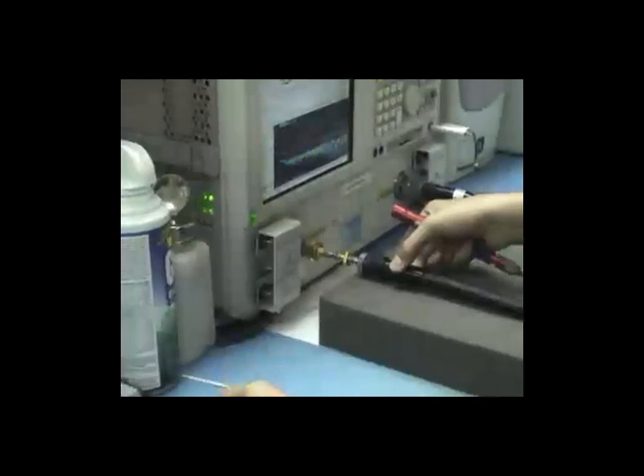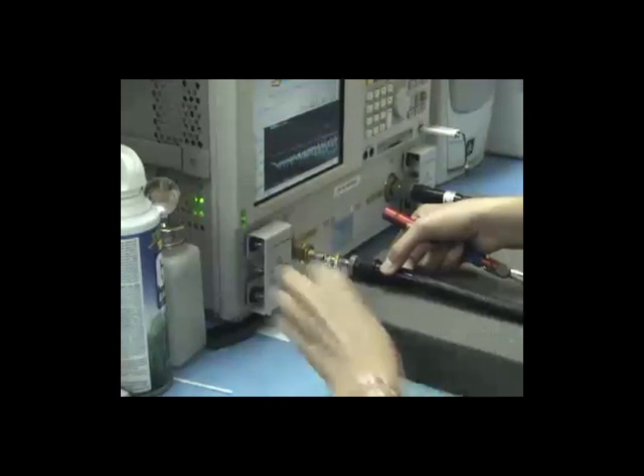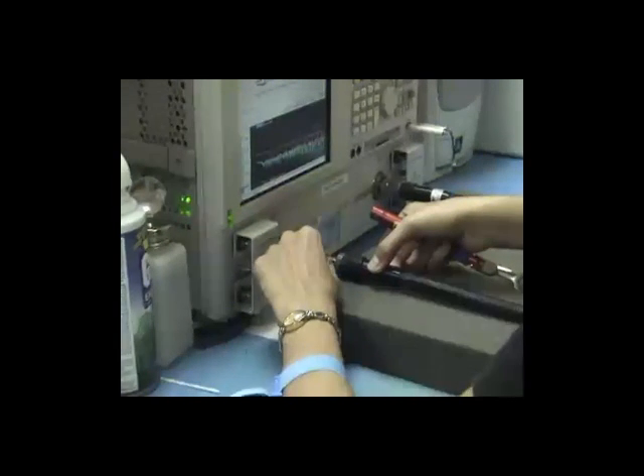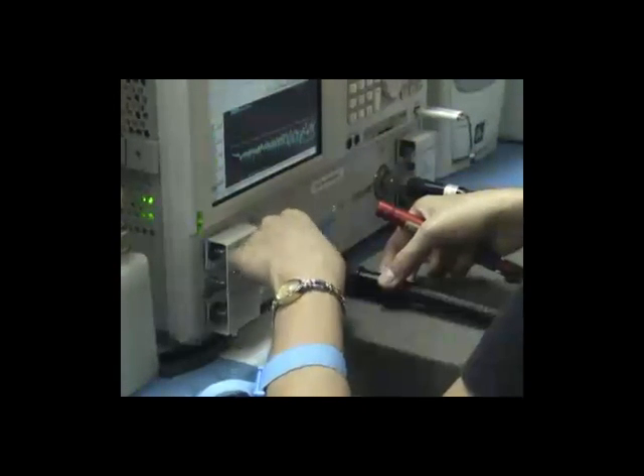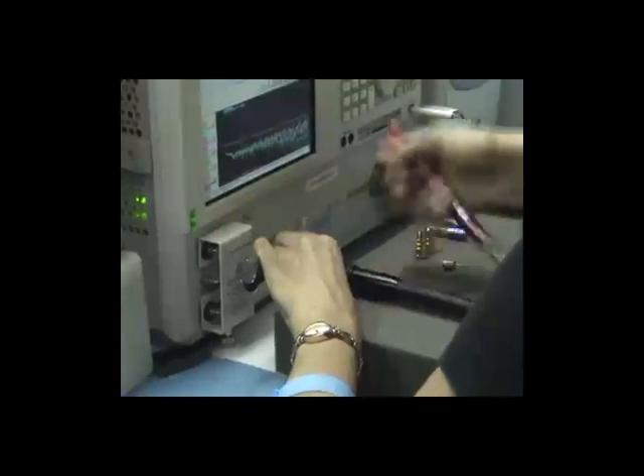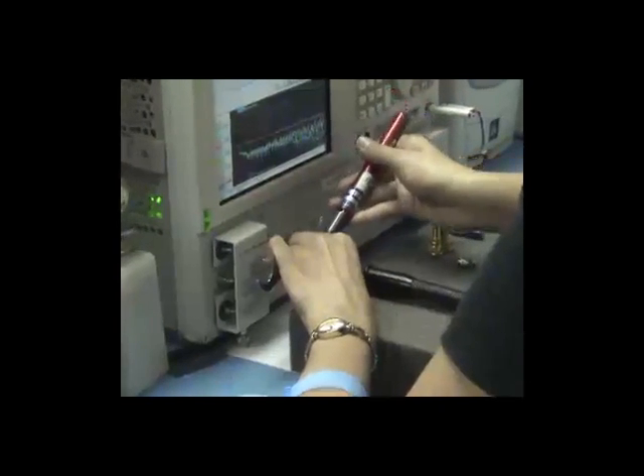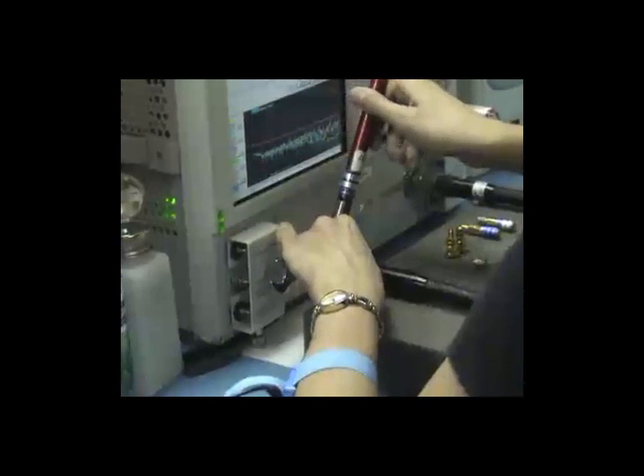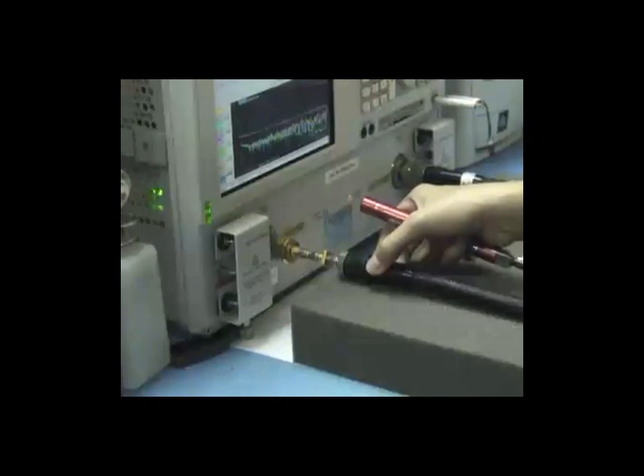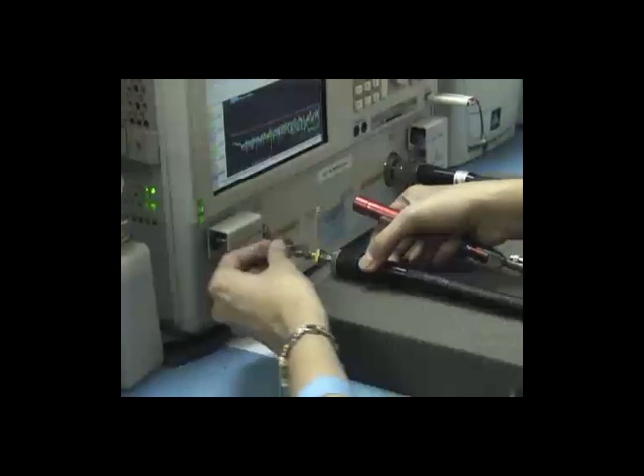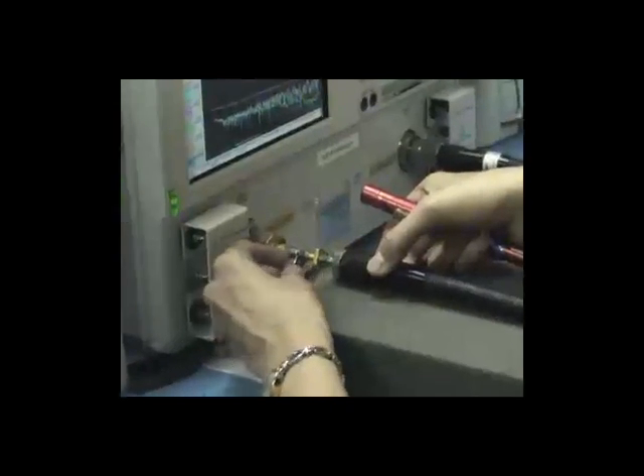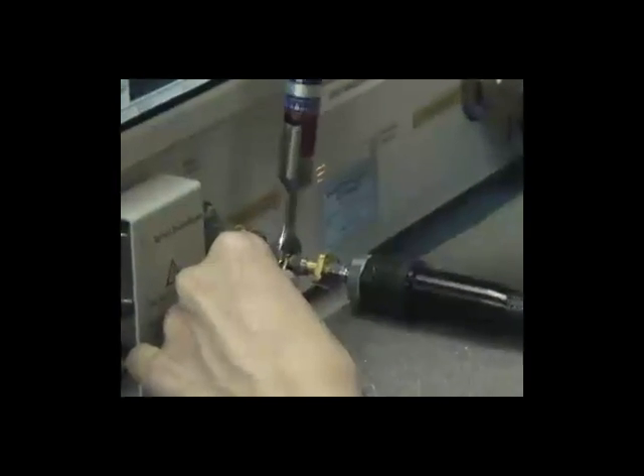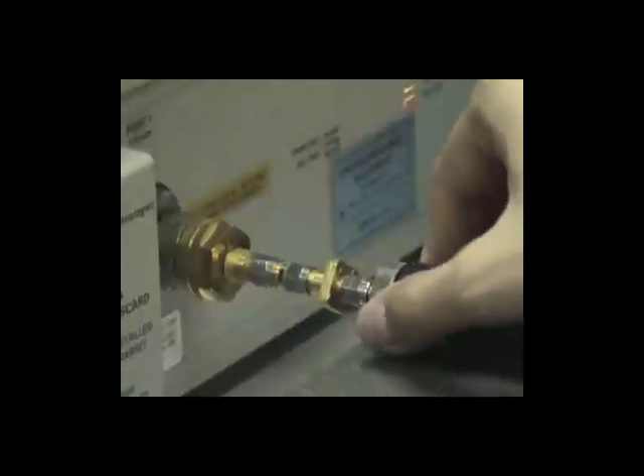Make sure you're always supporting it until you have torqued both sides, because if you haven't torqued and you let go one side, the weight of it is going to pull it. The reason why I generally go and check my torque on the other side after making this connection is sometimes it could loosen the other side, so I'll just go back and torque it to make sure I have a good connection.